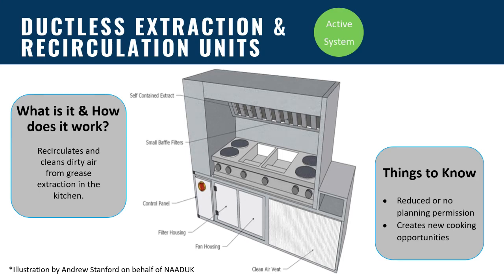They still require some filter and canopy cleaning and some duct cleaning within the system. They can be used in conjunction with another pre-filter system such as wool. Many of the units do not control air temperature, so they're not air conditioning. Only to be used with electrical catering equipment, as most units don't remove carbon dioxide or products of combustion from the recycled air. And they're a great alternative to high-level discharge. They do require periodic maintenance and filter changing, and the capital investment required is high, but there's an option to lease and to relocate the equipment.